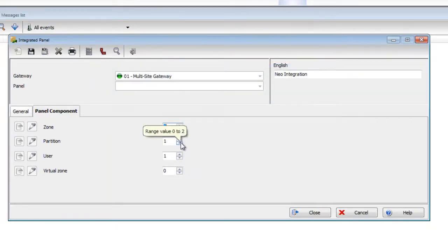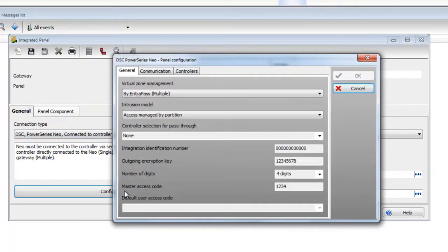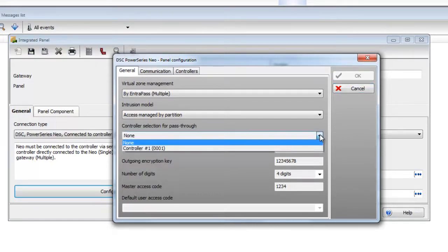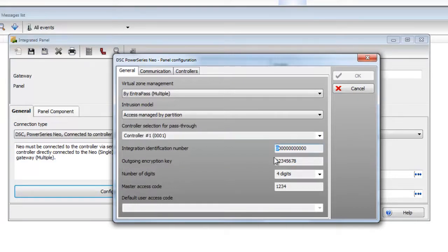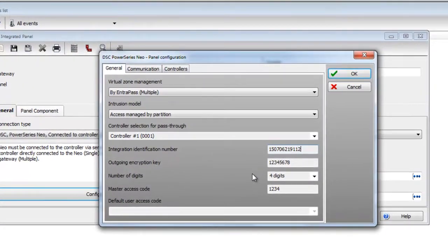Then we go to the panel components. We can see our zones, partitions, and users. You'll want to configure this in EntraPass beforehand — and also the virtual zones, which we will cover in another video. Once that's done, click the configuration button. First, select the controller for pass-through — we're going to select controller number one. Then we have to enter the integration identification number, which we got earlier from the NeoPanel. Go ahead and put in all 12 characters.